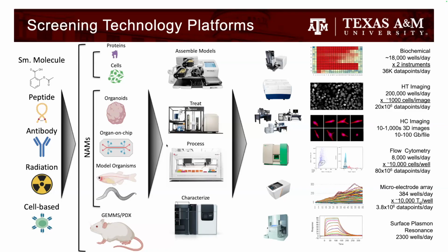Our microelectrode arrays, again, we can work on the electrophysiology of neurons and cardiomyocytes, but we can also look at scratch assays, for example, or anything with cell growth, because the impedance is actually transepithelial resistance, so it's a TEER measurement. And so we can look and see what happens with monolayers of cells that grow on the electrodes.